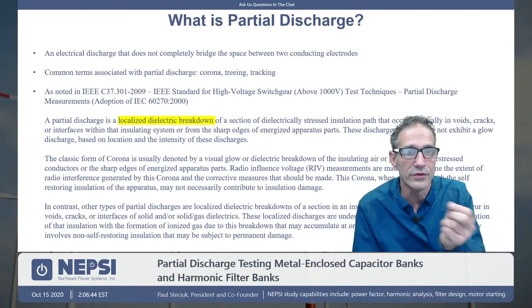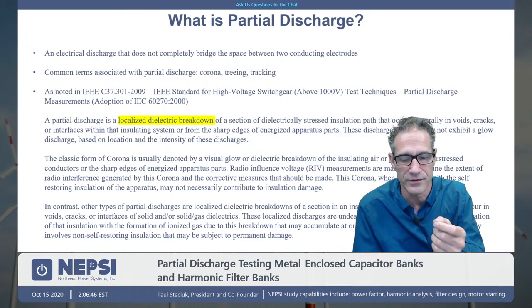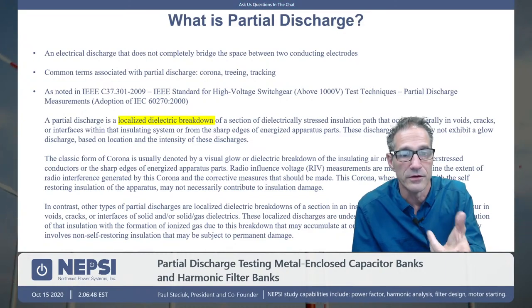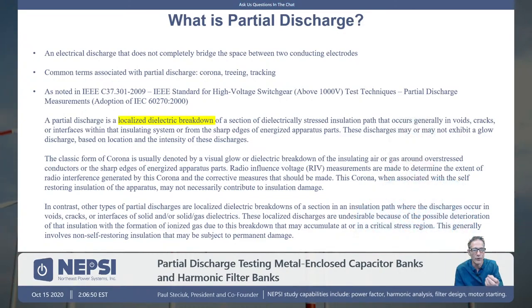It can also occur inside the insulation if you have, say, a bushing, and there's a void within the bushing. You can have partial discharge within that void, but it doesn't result in a flashover. Oftentimes, when we are doing high pot testing, withstand testing, we're bringing, say, a 34.5 kV piece of equipment up to 80 kV. We'll hear a lot of partial discharge going on. It will be making a lot of sounds.